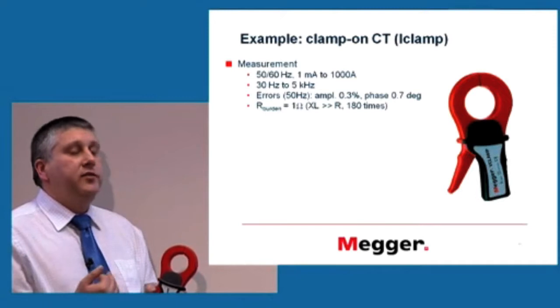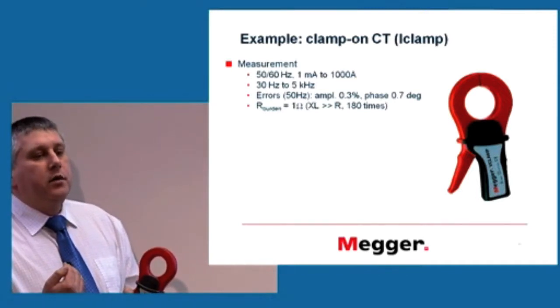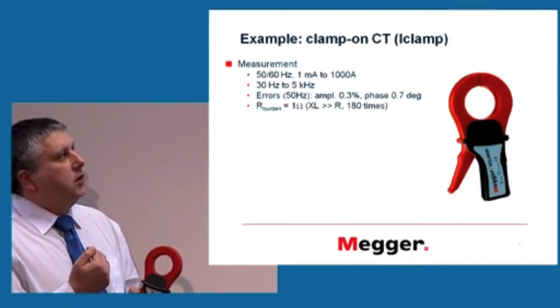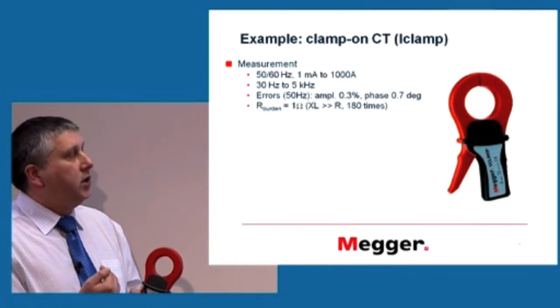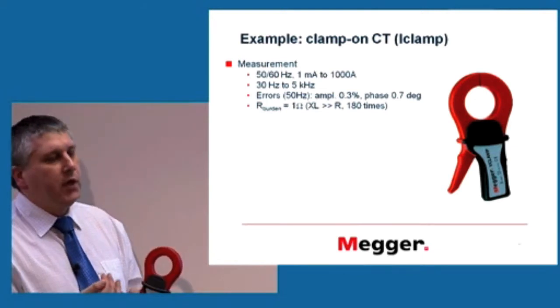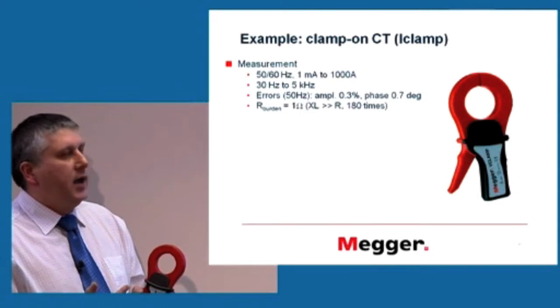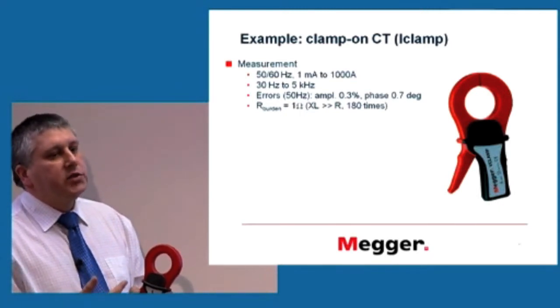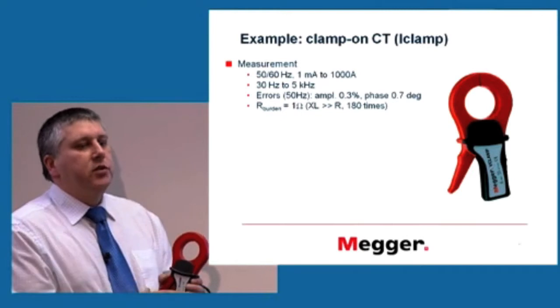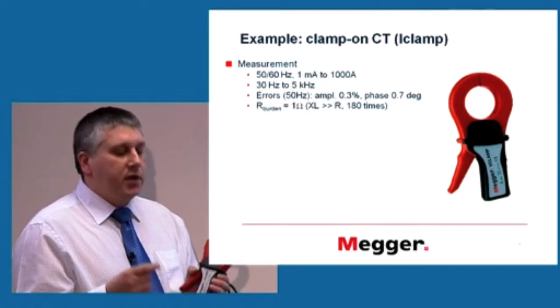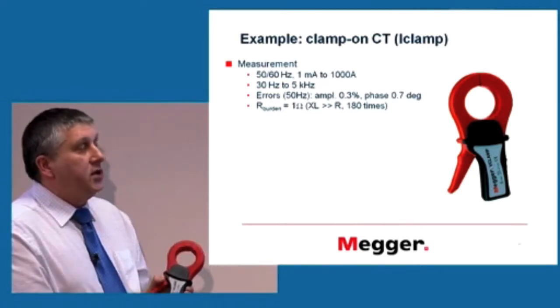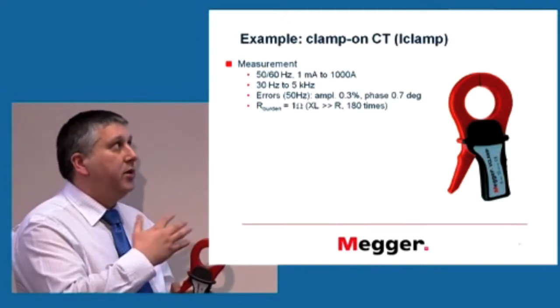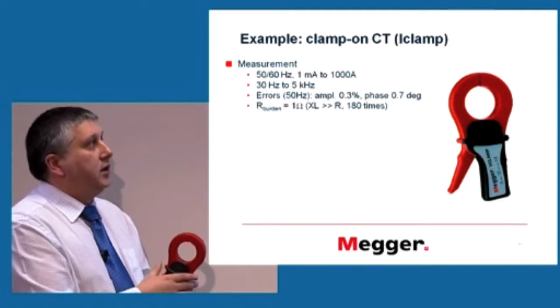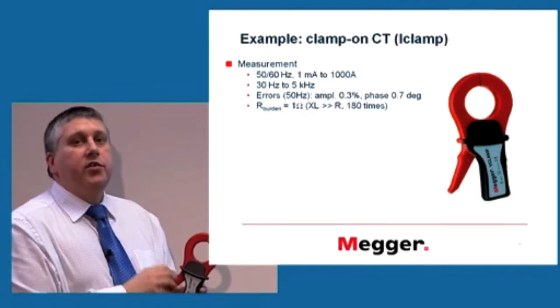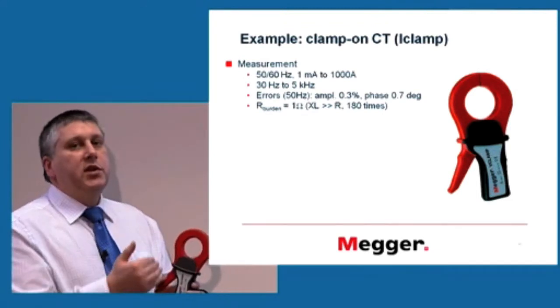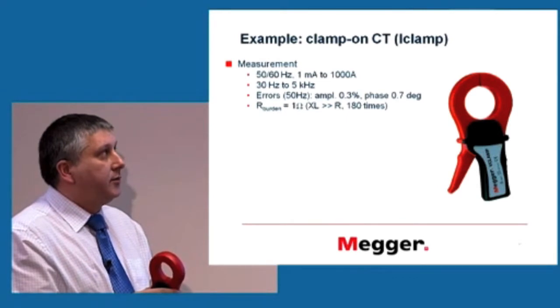In order to achieve that proportionality, the burden has to be 1 ohm. It cannot be more than 1 ohm, and this is because, as I said before, the impedance of the secondary winding has to be much greater than the impedance of the load. And in this case, it's at least 180 ohms. It can be more, depending on frequency, of course. And that's why it limits it at the 30 hertz, because if we go lower, then the impedance drops, and that condition is no longer met.